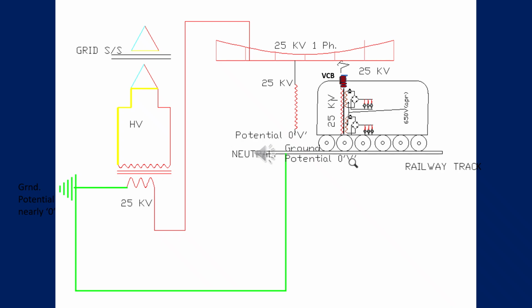But the body is at ground potential. The top portion is through the insulator, but the bottom portion, that is zero potential, is connected with the body. So it will not harm, because the body is fully connected through the wheel to the railway track, which is at ground potential. So the whole locomotive body is at ground potential. If the OHE falls on the locomotive, the current will follow the low resistive, low impedance path, so your body will not get shocked. The current will flow through the wheel to the circuit breaker, and our circuit breaker is so fast that within a few seconds it will trip and power will be switched off.